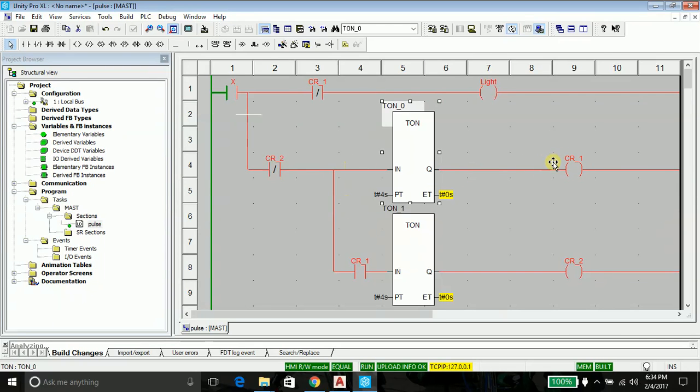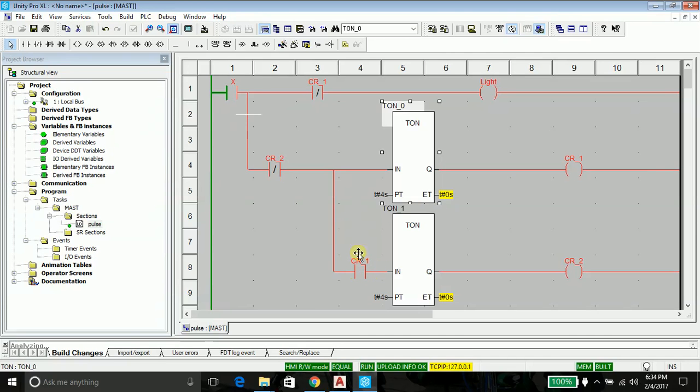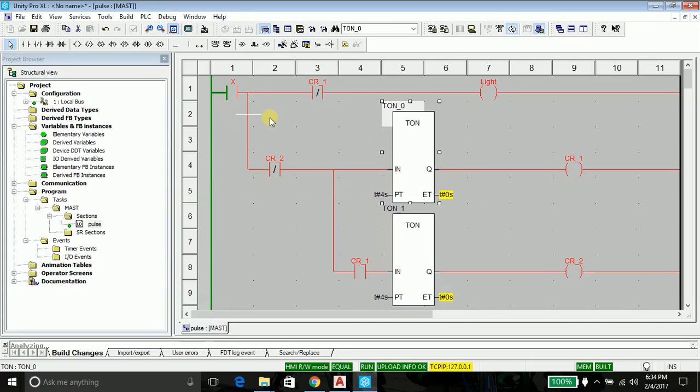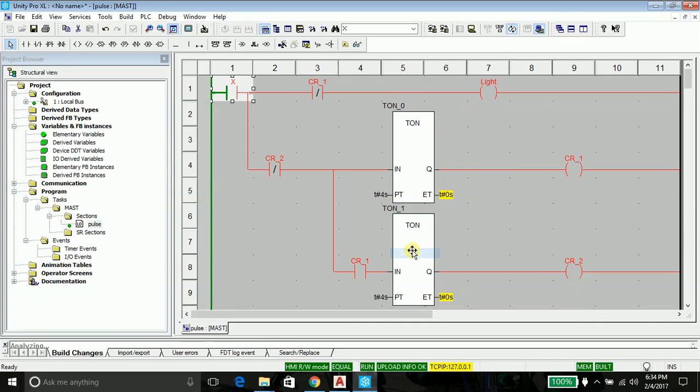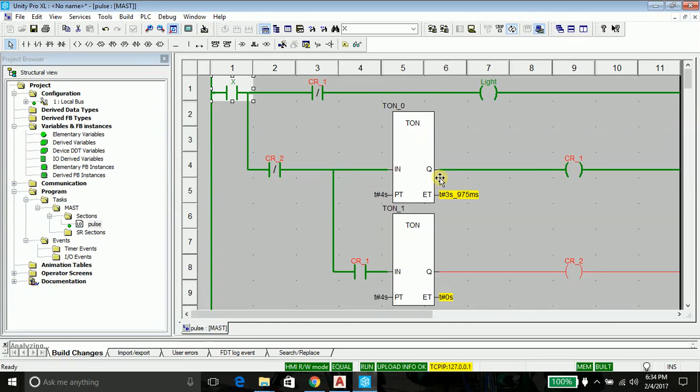And at the same time, when this coil is energized, it will energize this contact. This contact is a normally open contact—it will become closed and start conducting the current and activate this timer. And this timer, after four seconds, will produce output and energize this coil. And when this coil is energized, this will reset this timer and everything else.